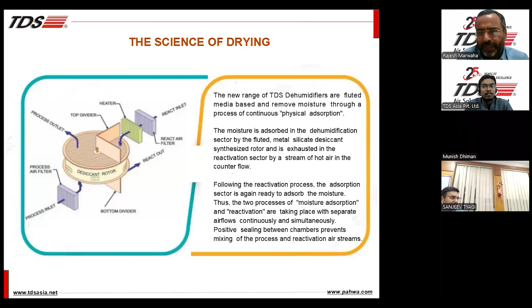And this rotor is a metal silicate desiccant synthesized rotor, and has the highest efficiency to absorb the moisture. This is the heart of our desiccant dehumidifiers, the photographs which we have shown earlier. And depending upon the capacity of the machine, the rotor size also increases.